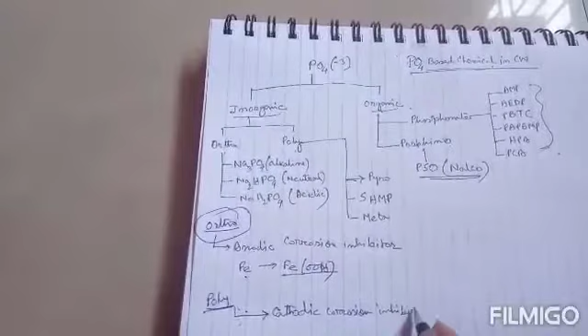Now comes poly. Polyphosphate has two functions. One is cathodic corrosion inhibitor, second is scale inhibitor. So polyphosphate basically acts on both areas. Cathodic corrosion inhibitor, how does it work? At the cathode, at local high pH, it provides calcium polyphosphate precipitation on the metal surface, and it passivates the cathodic area. That's how it provides cathodic corrosion inhibition.